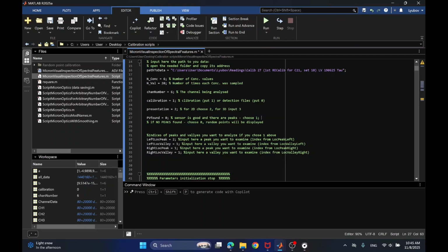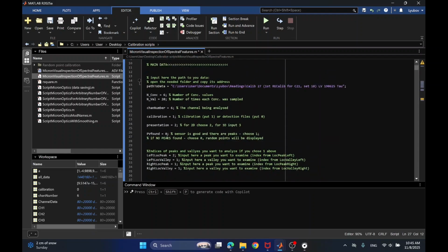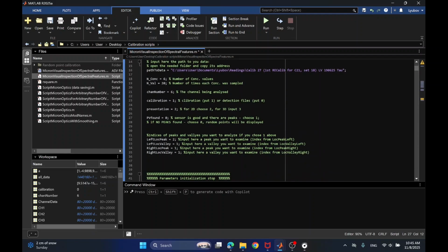The next step is also important. You see, in the case of this probe and this calibration, we are supposing it doesn't have any peaks and valleys worth speaking about. So you input 0 here. It tells the script that there are no peaks and valleys, and it should look only at random points to see if there is some sensitivity which got undetected. So we will run the script after all the settings are made, and we'll see what it gives.